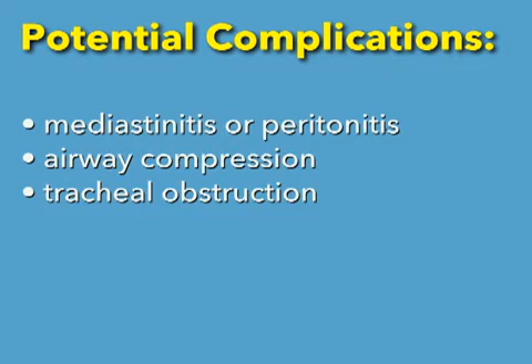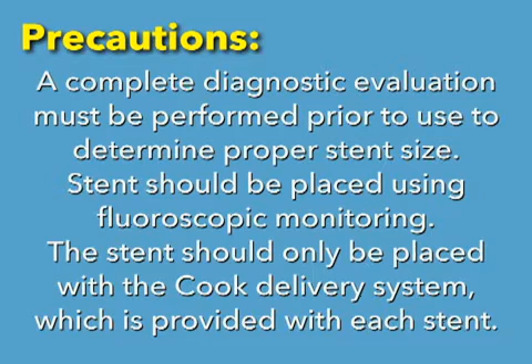Precautions. A complete diagnostic evaluation must be performed prior to use to determine proper stent size. Stent should be placed using fluoroscopic monitoring. The stent should only be placed with a Cook delivery system, which is provided with each stent. Prior to advancing the system, the area to be stented should be dilated to a minimum of 10 millimeters and a maximum of 14 millimeters. If the area is dilated greater than 14 millimeters, the stent may migrate.